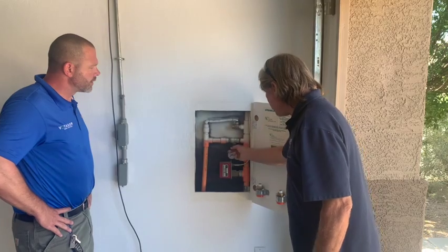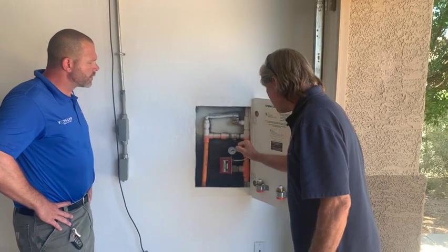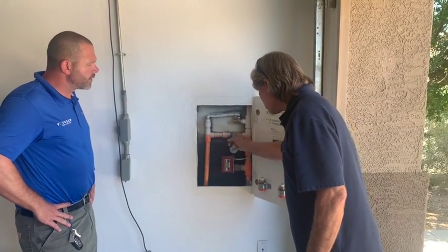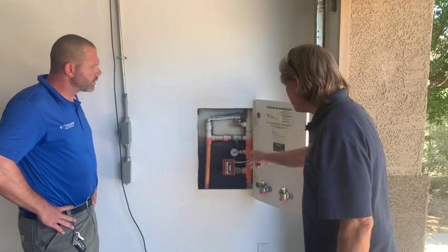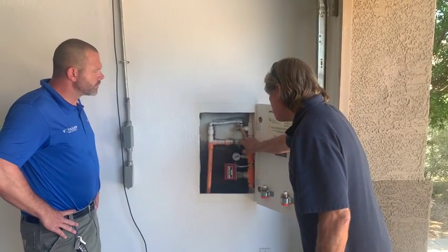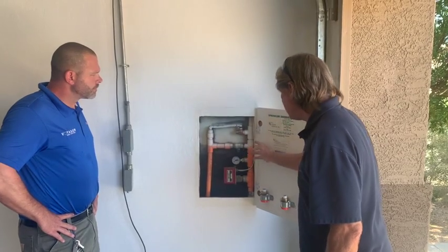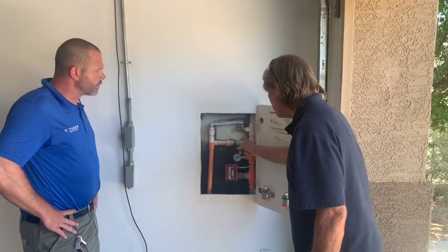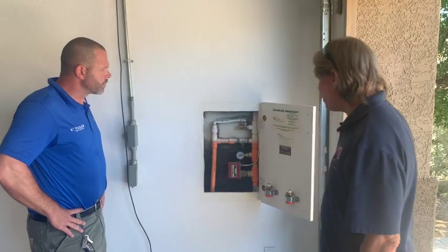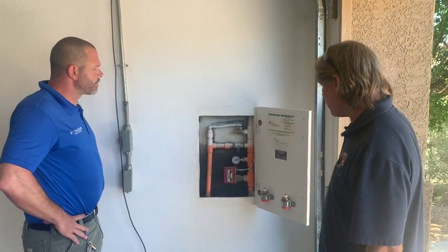This main drain valve here, in this case a ball valve, also comes to the same point. And so either one or sometimes both of these are defective, and in that case I usually have to rebuild the riser and replace both of those components to restore the integrity of the water.